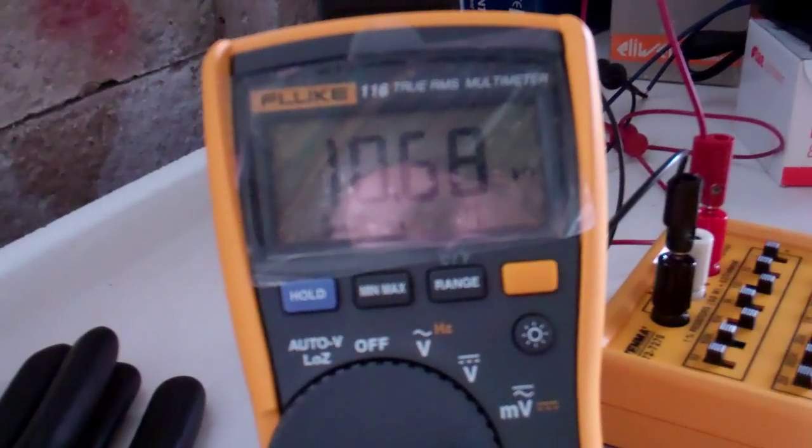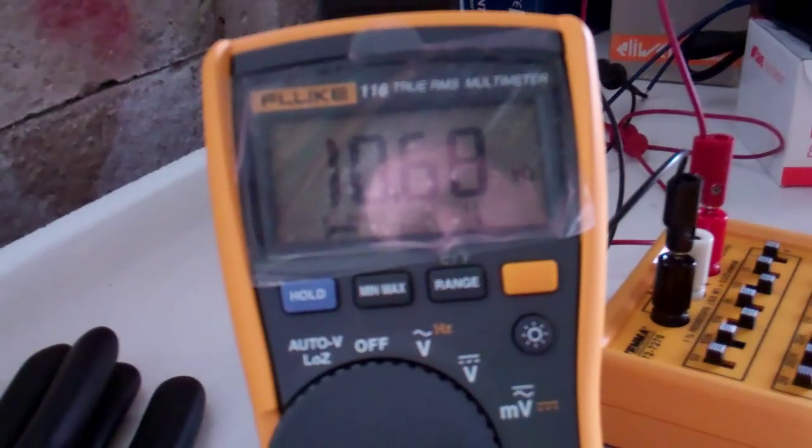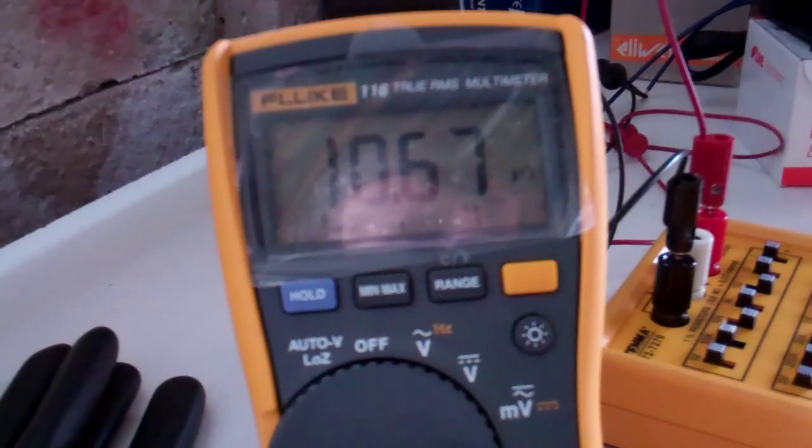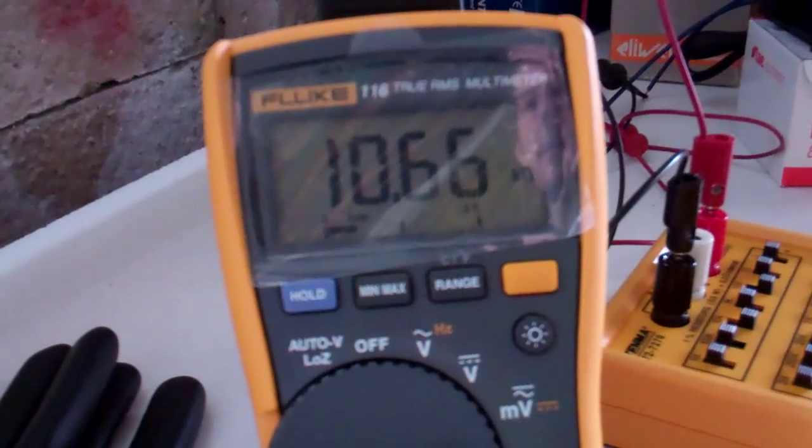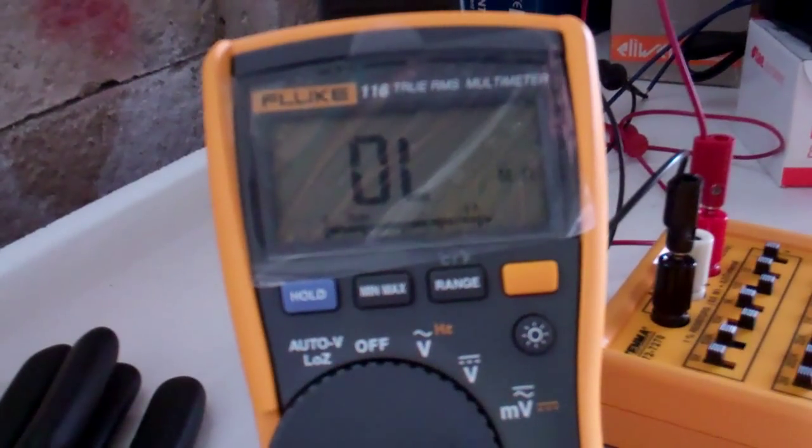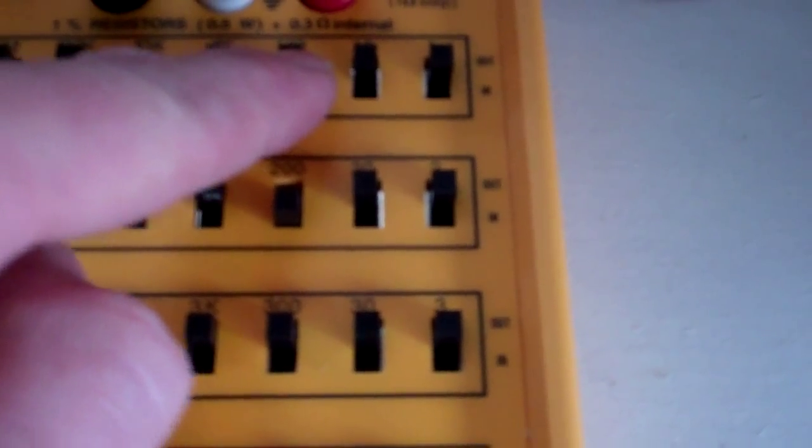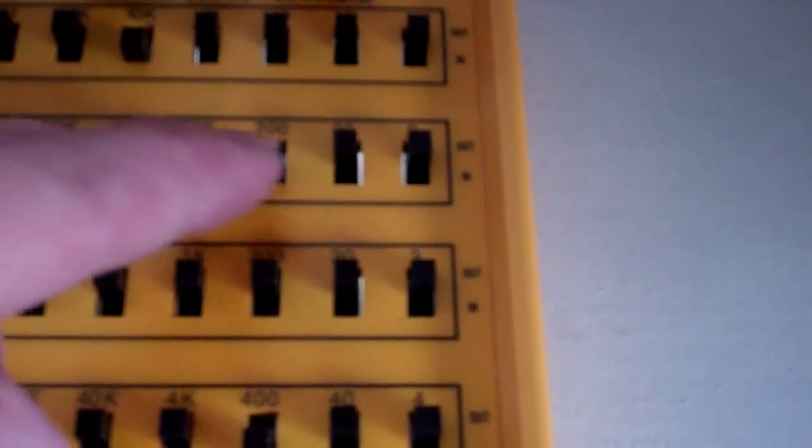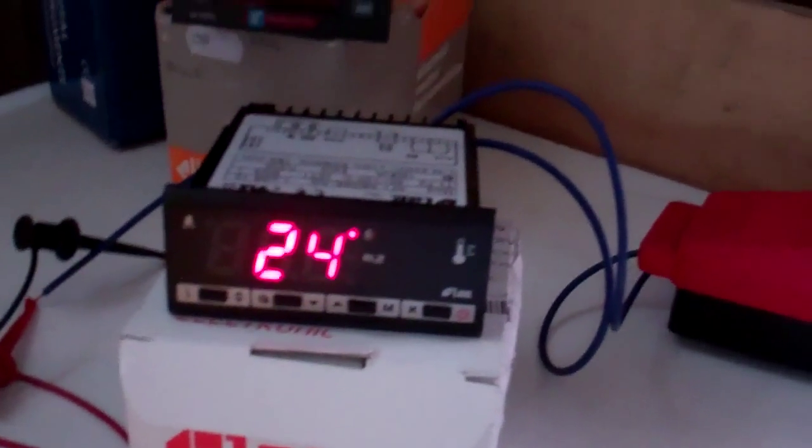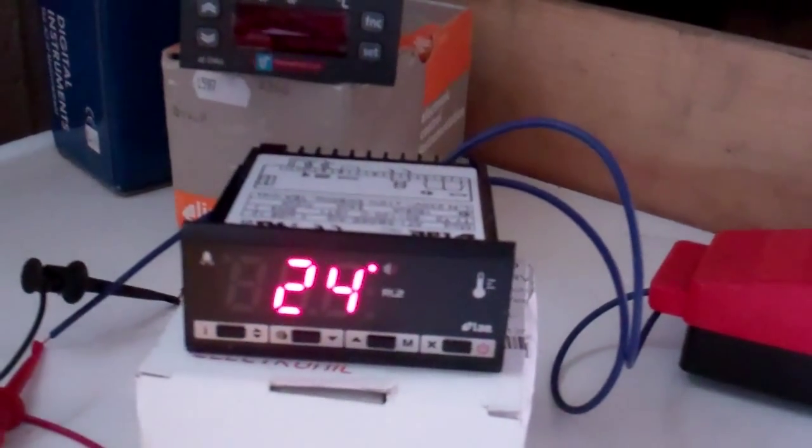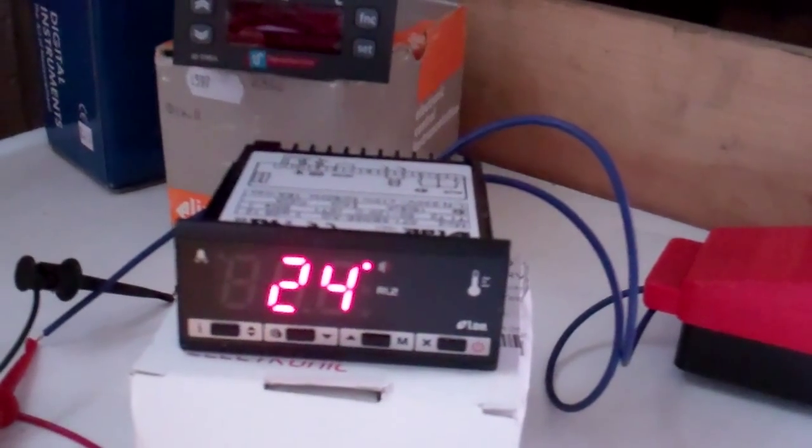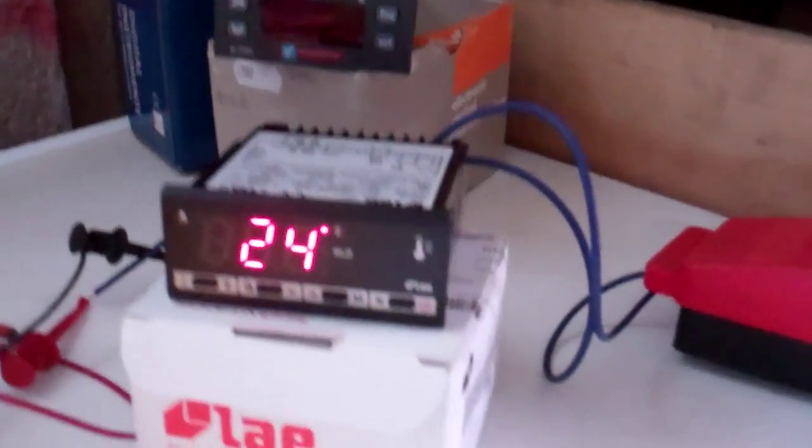That's saying 10 point, it's in kilohms. I'm saying 10.6. So actually we could say those at 10.6. 10, 100, no 10, 2, 4, yeah, 10.6. So according to that it is 24 degrees in there.